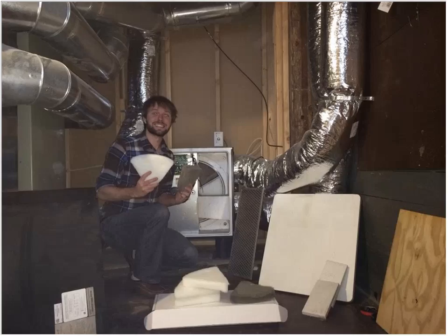So that's me with my energy recovery ventilator. These are devices that can help with balanced systems in a home. It's not the only system you can use to do a balanced system. There are other systems out there that can use exhaust fans and ways to open the furnace damper to do a balanced system, so you've got as much air coming in as you have going out.